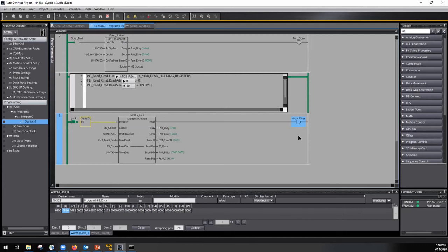So in Modbus, this is something that we need to keep track of and do something if it happens, right? This could be an alarm. If I attempt, say, 10 times to do a function 3 read and I don't get a completion bit, then notify the operator or reopen my socket, take a break, flush the Ethernet port. There's a number of things you can do, but that's just something you need to be conscious of when you're doing a connection like this. Any questions on the Modbus side?